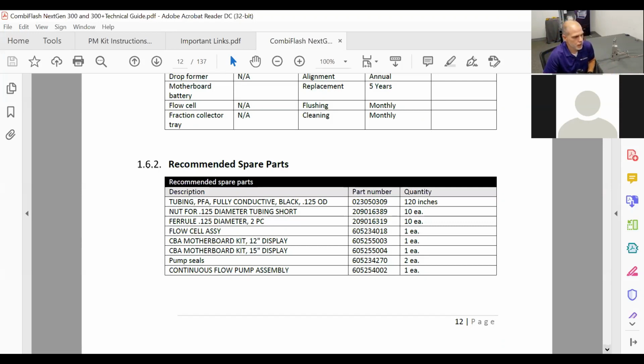The tubing, there's a lot of black conductive tubing. The reason it's conductive is because hexane can carry a static charge, so our tubing dissipates it. Some of the other solvents you may use do the same thing, but hexane is the big one. If we don't dissipate that, it can just continue to build up a static charge. Hexane is flammable, so just take care. Make sure you're using any of the fully conductive black tubing.